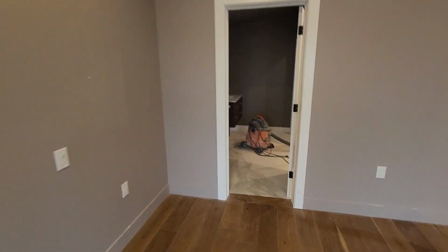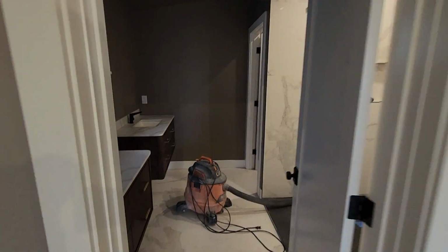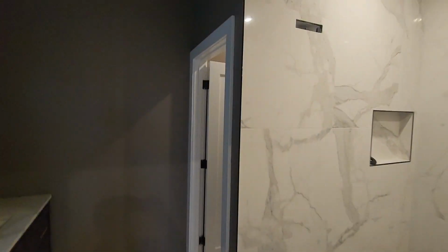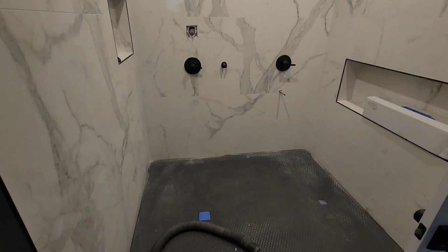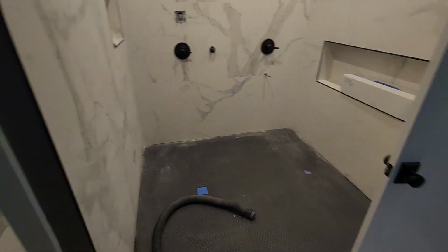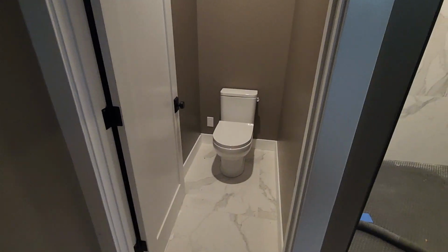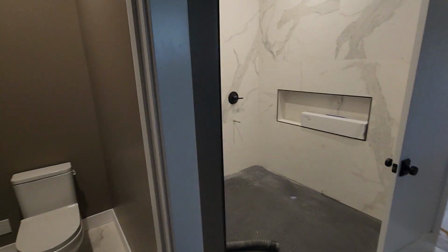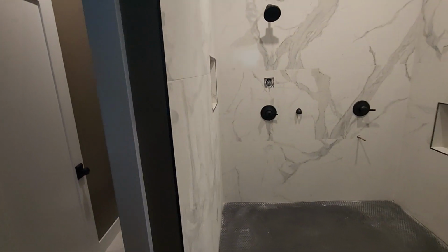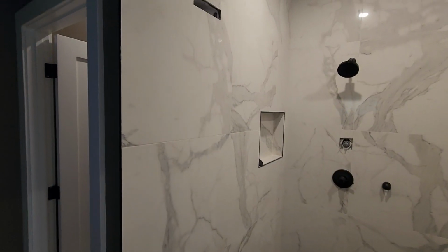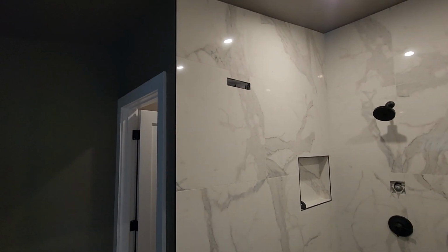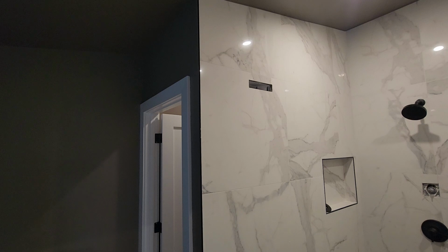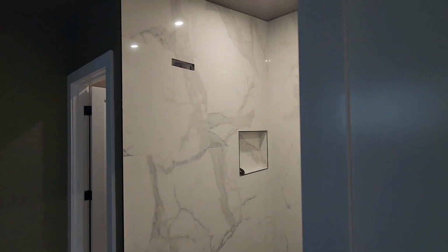And then I'll show you the hardest room here, which is the bathroom. So this is the furthest from the house. It's a walk-in shower, and there's the bathtub there, and then again a separate toilet there, and then we ventilate from right there. So these two are the furthest from the unit. So this is kind of what I work on, is getting these up as close to or over 10 CFM on each side for code minimum.